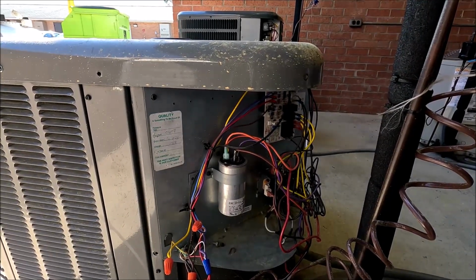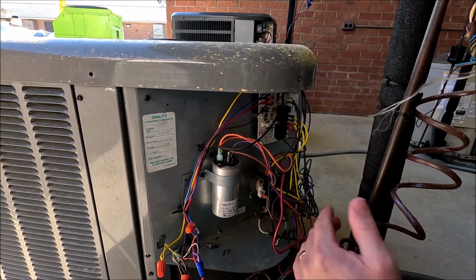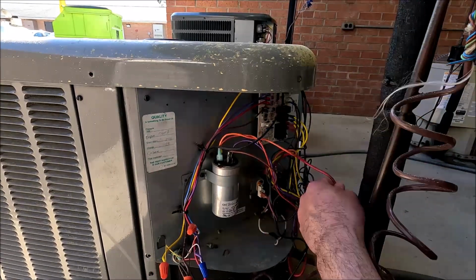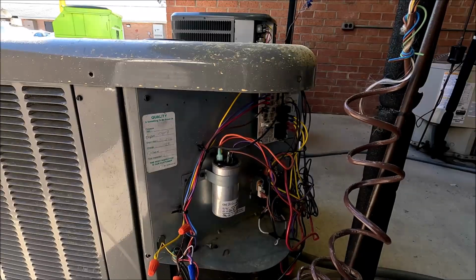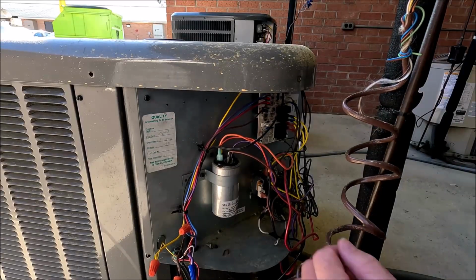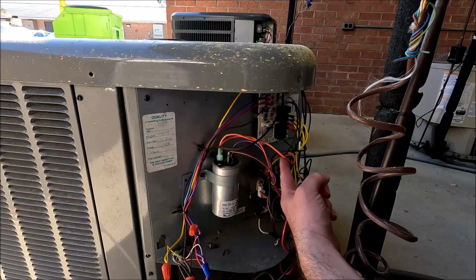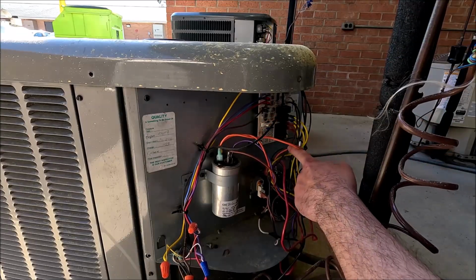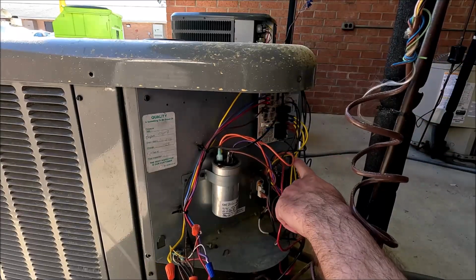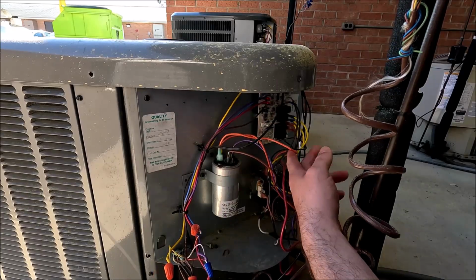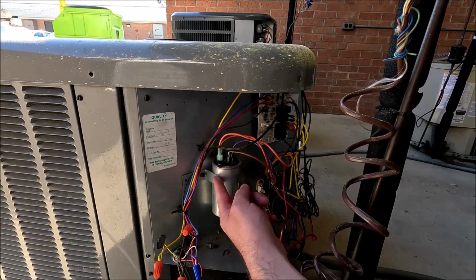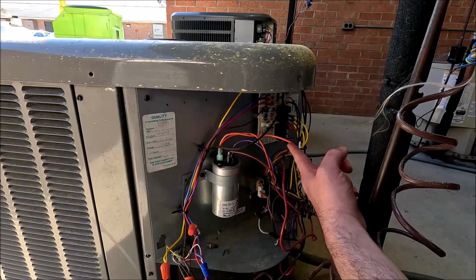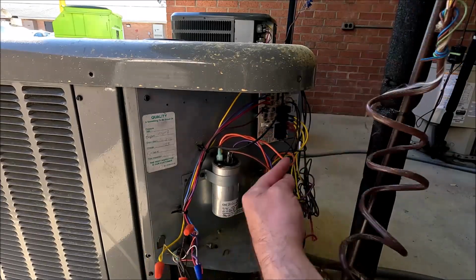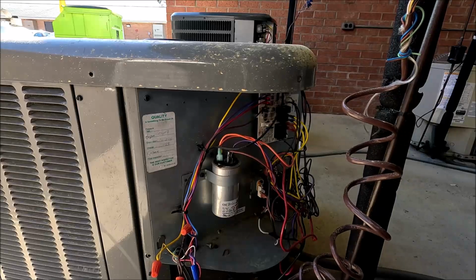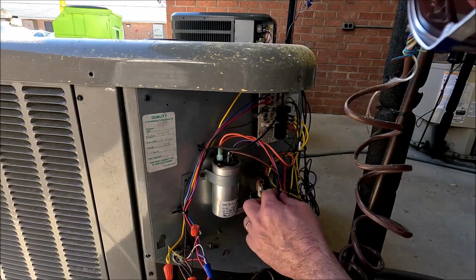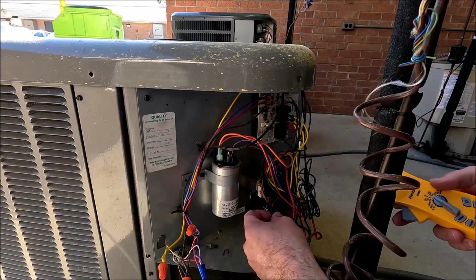So more wires, more wires, more wires. And you can look down here and you can see the oranges and the reds and everything. And once again, I look for this capacitor and I see this orange wire that goes from the right side of the contactor up and into the capacitor. So I think that this is my L1 side, and it's on the right side of the contactor. So what I can do is, to get my amps on the outdoor fan, that's this black wire right here.